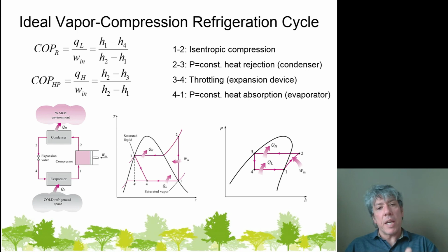That's how we end up at a state 4, that has still some liquid but a decent amount of vapor in it. And so at state 4, we still have some liquid that can boil off. So typically these refrigerants are down around 50 degrees if we're talking about a home air conditioning system. So state 4, there's still some liquid, in fact quite a bit of liquid, available to be evaporated. So this is relatively low pressure, low temperature refrigerant that's ready to absorb heat from the air or take on thermal energy because it's at 50 degrees.